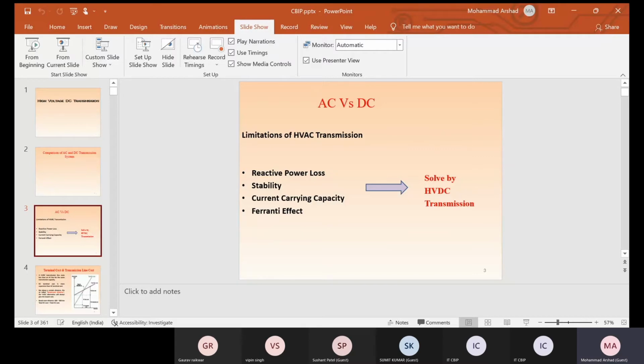In AC, the Ferranti effect is also there. If your line is lightly loaded, due to the Ferranti effect, more reactive power from the capacitance between the line and ground causes more charging current, more reactive power supplied, and the voltage becomes higher. All these issues are solved by the DC transmission system.